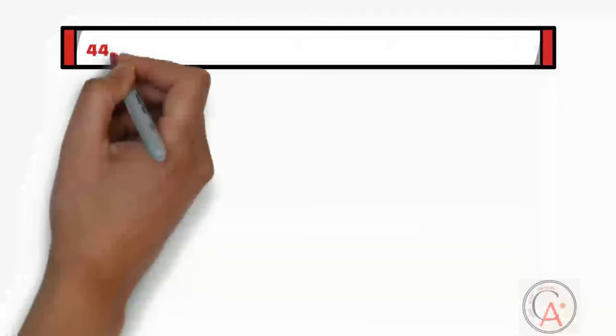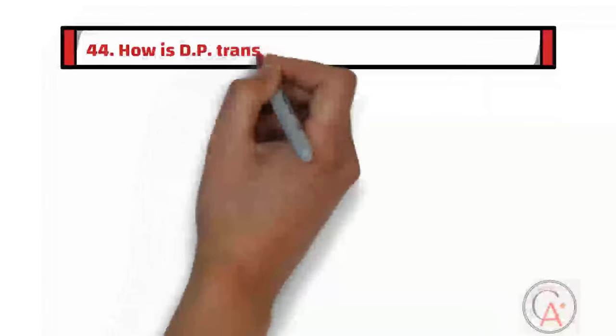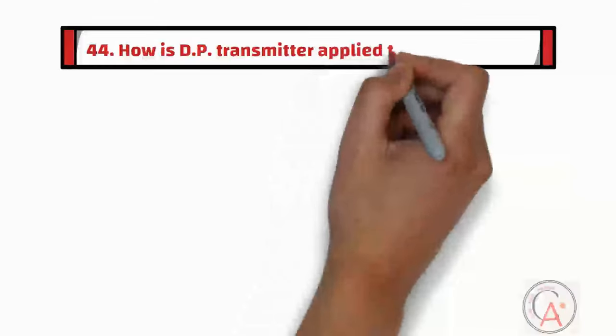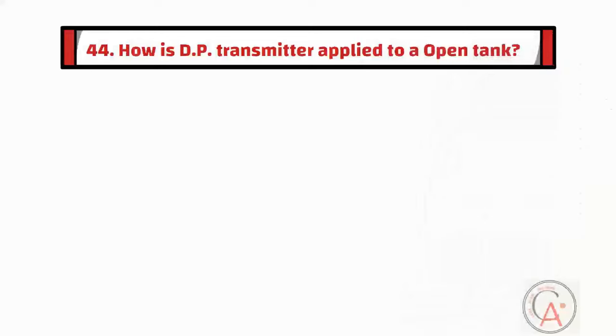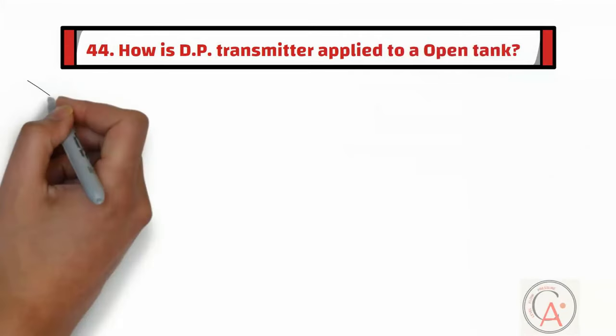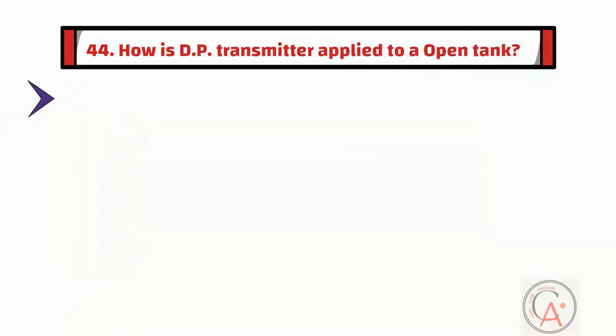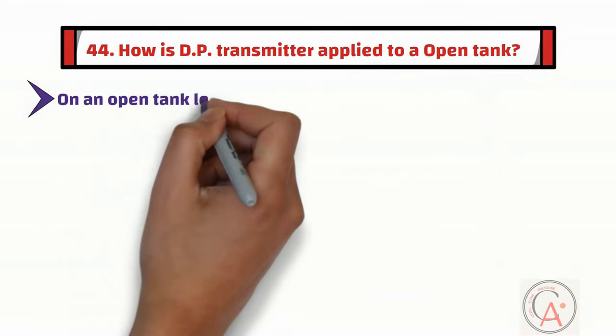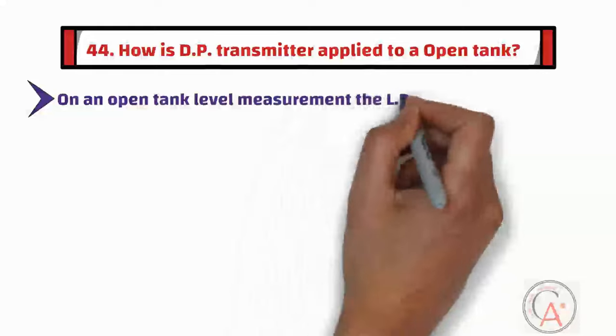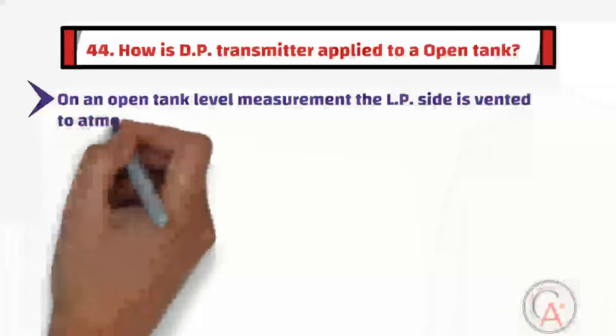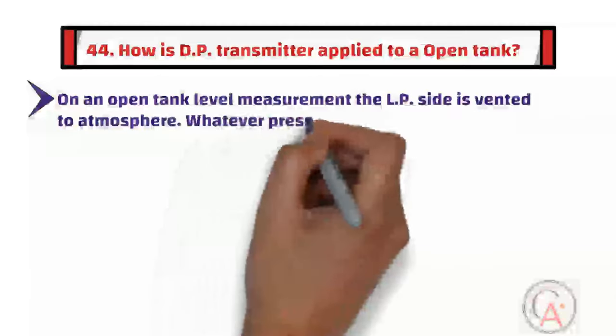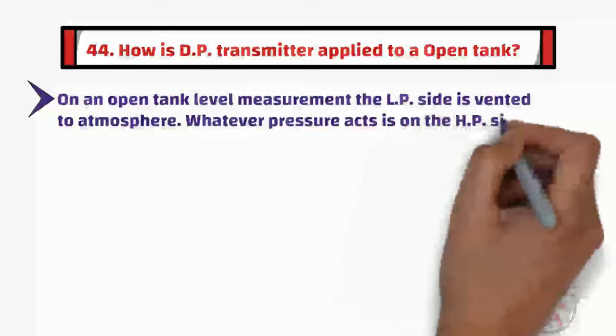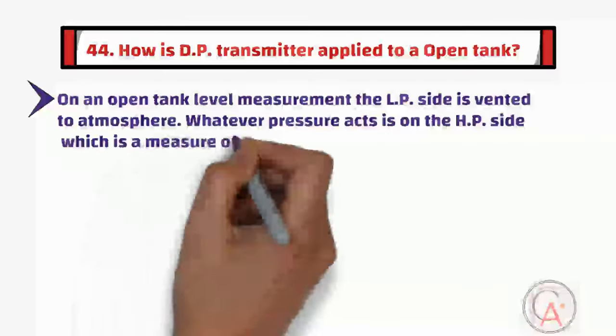Question forty-four is: how is a DP transmitter applied to an open tank? In an open tank level measurement, the LP side is vented to the atmosphere. Whatever pressure acts on the HP side is a measure of level.